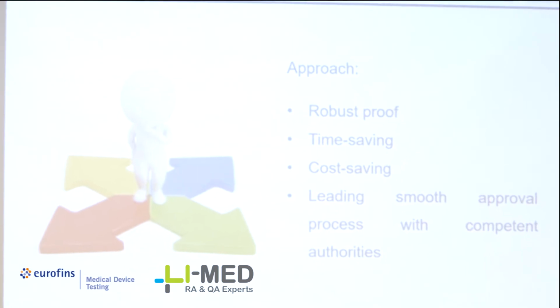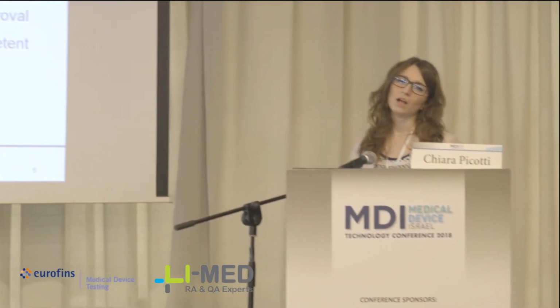But how can they demonstrate it? How can they satisfy the safety requirements according to the regulation? Basically, there is no mandatory pathway to be followed. I mean, from a theoretical point of view, a manufacturer can do everything he wants to demonstrate the safety of his device, but for sure, he needs to apply an approach that is time-saving, cost-saving, and that should give a robust scientific proof of safety, and should lead to a really smooth approval process with the competent authorities to obtain the CE mark, for example, or to succeed in an FDA submission.